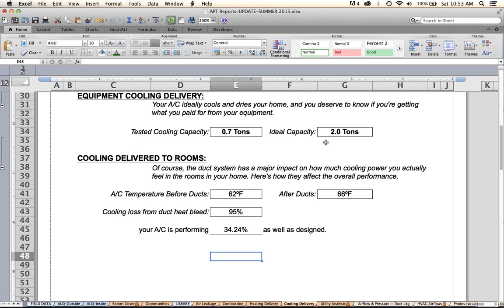Now, one of the things that I'd like to make sure of, and I will be testing this in a brand new building that I'm commissioning, which is going to be part of the subject of the Mastermind webinar on Wednesday, is making sure that this number on a brand new, excellently performing piece of equipment is actually going to be as close to 100% as possible. Because I don't want to give you guys the ability to go out and start telling people, oh, it's only 34%. And then when you fix it, it's like 60%. Well, that still sucks. So anyway, you can see basically where we're going with this.